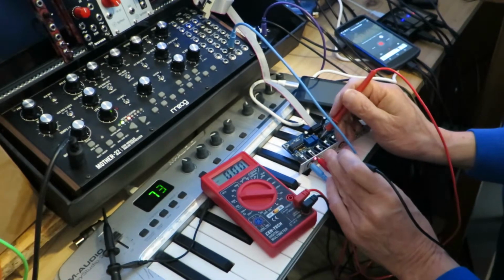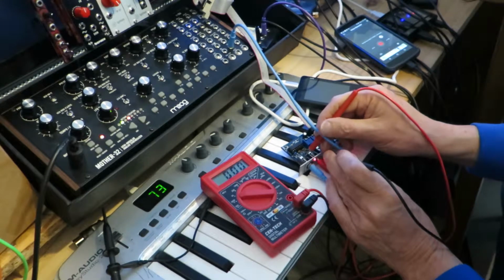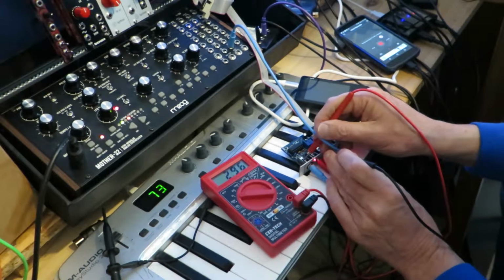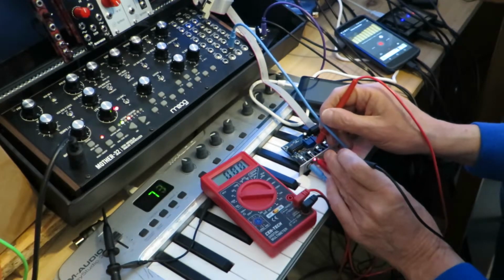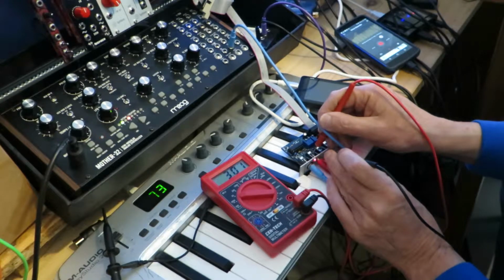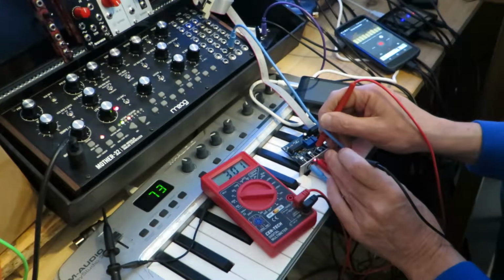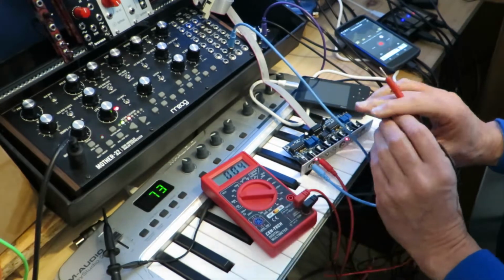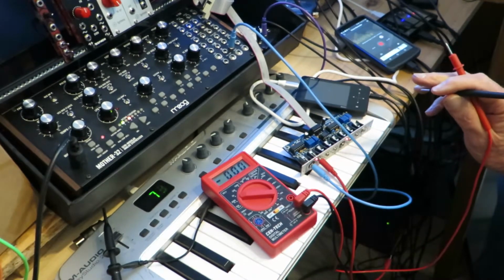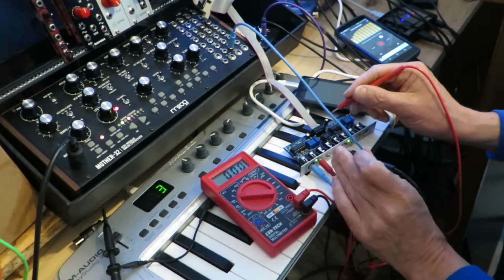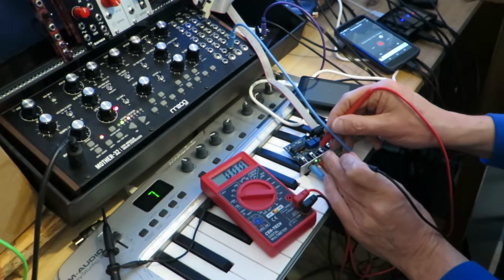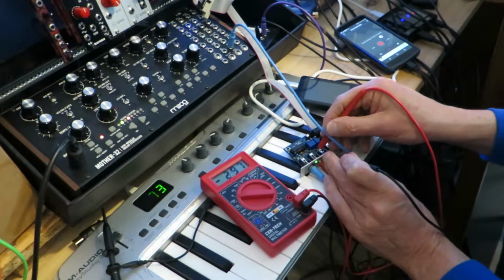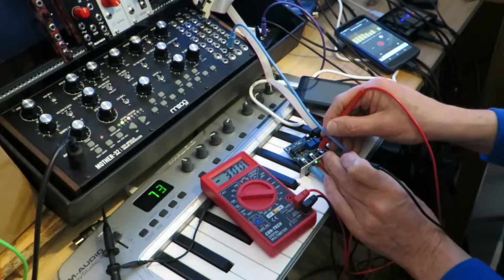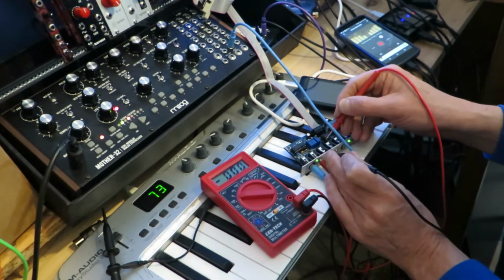Measuring from ground to input tip, we've got 2.96. Ground to output tip, I got 3.01 because I have changed the calibration. If I go to 3 octaves below middle C, I've got minus 3.00.